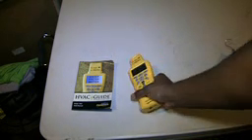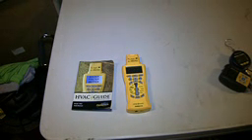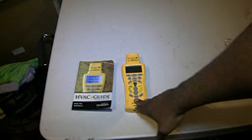Now, what I've learned to use with this HVAC guide, like in one of my other videos, is I sync it with my S-Man 4 manifold gauge, so I can verify what the pressures are doing outside while I'm inside the house. Or let's say I charge the system up with nitrogen and I want to see if it's holding, but I don't want to wait there to see if the pressure drops. I charge it up with nitrogen, go inside the house, tidy up, button up, finish what I'm doing on the inside, and while I'm doing that, I can verify whether the pressures are steadily dropping.